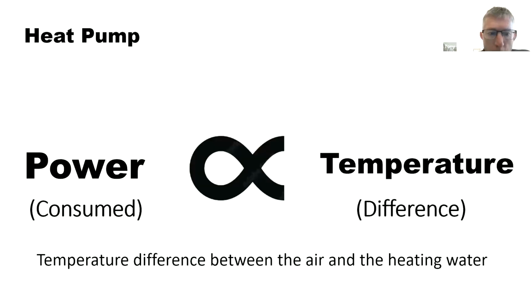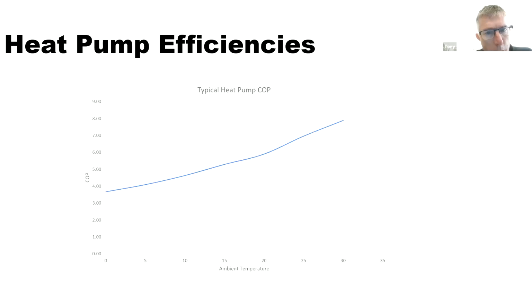And I'll explain that again, that the temperature difference between the air and the heating water in this particular case, well, in the heat pump case for aquatic centres. So with aquatic centres, this is just a standard heat pump that we could use in an aquatic centre, and you can see that the COP will differ depending on the ambient temperature. And obviously, as it gets warmer, the efficiency improves, the COP improves, which again is similar to the capacity. During the coldest times when you need the most heat, it's at its least efficient.